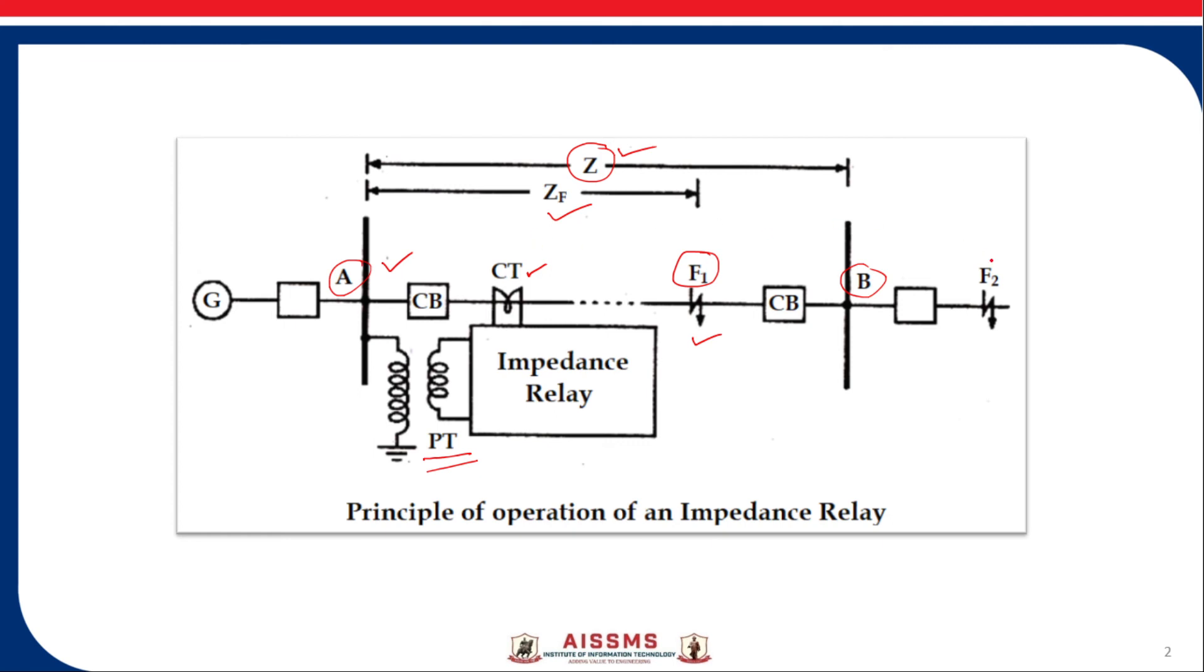For the fault F2 occurs beyond the protected zone the impedance ZF will be greater than Z. In this case, ZF2 is greater than Z and that's why the relay does not operate.